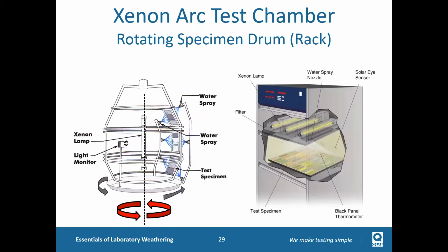So this is a Xenon Arc chamber. There are two kinds of structure of Xenon Arc chamber in the world. For some of you that may be familiar with the rotating drum, QLab also has a rotating drum tester, which is our XE2. In some markets like textile, people traditionally like to use the rotating drum, and QLab also has the rotating drum. And for most other applications like paint and some plastics, we actually recommend you use a flat array like this one.